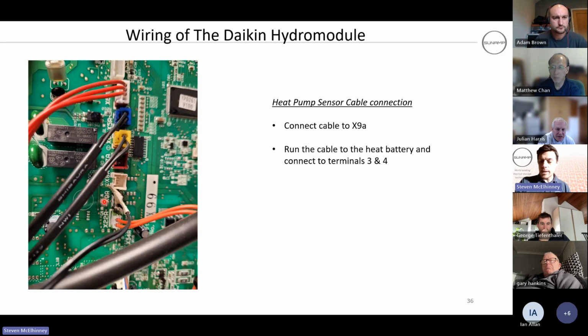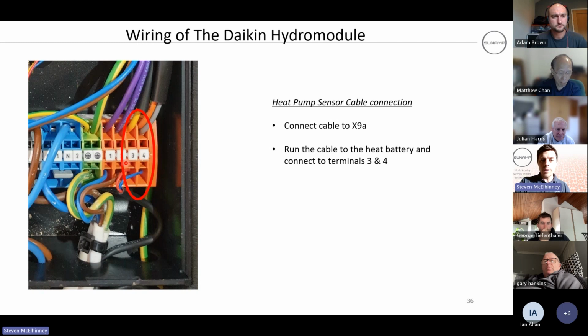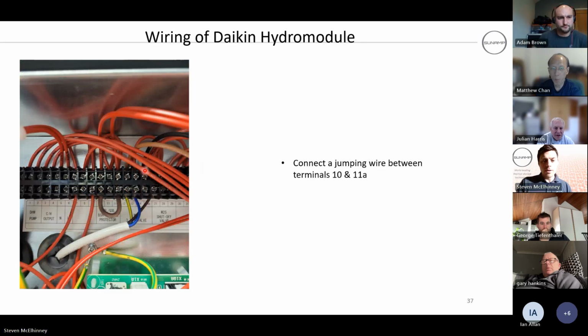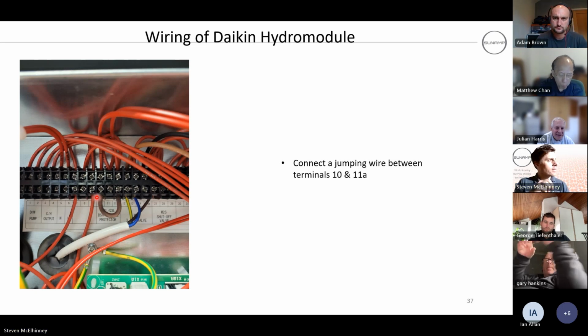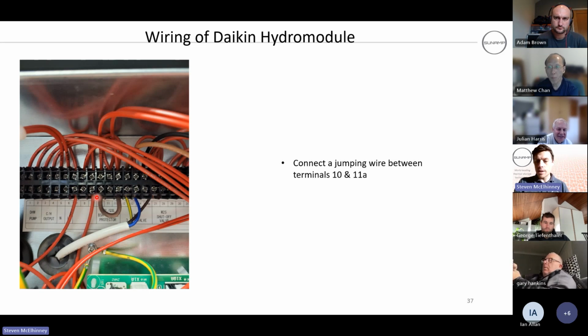So you basically run it from X9A into terminals 3 and 4, and that's your control circuit, so the battery can communicate with the heat pump. We'll talk about communication in a minute. And just remember to put a jumper wire in between 10 and 11A on the terminals up here. What that does is it disables the booster element for the heat pump, and it prioritizes our third-party element, if you like.